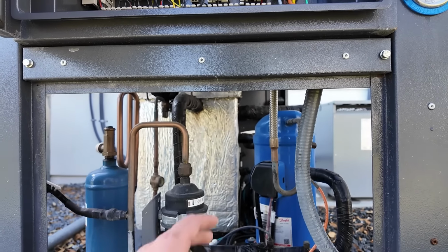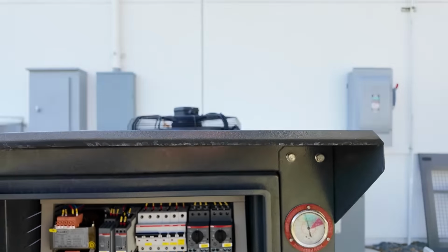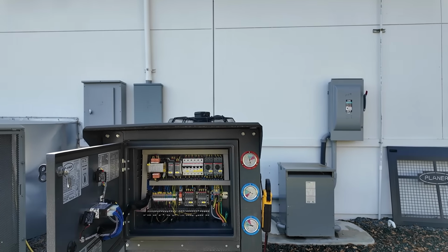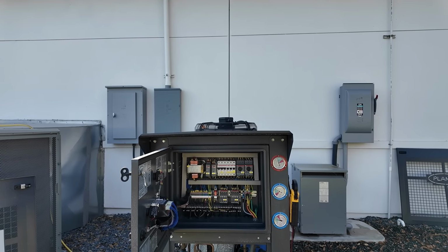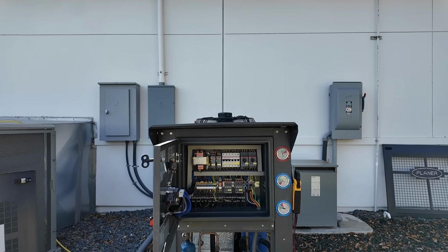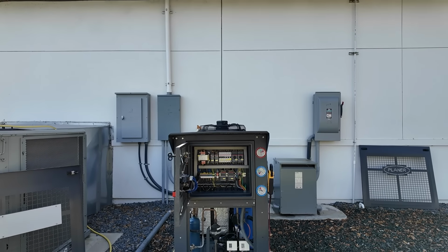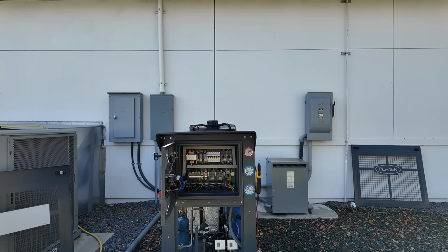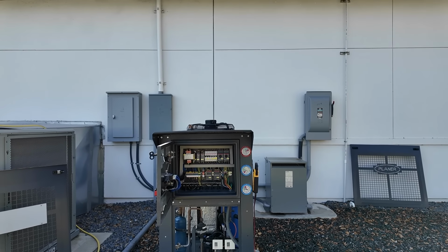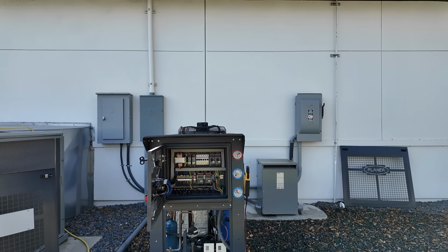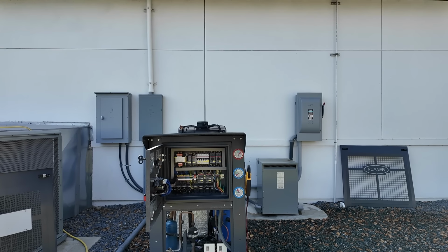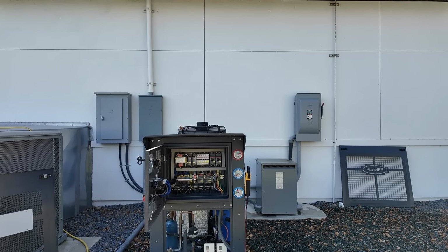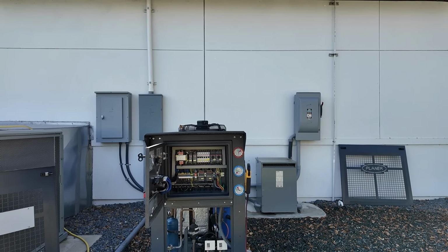Again, we don't recommend pouring water on high voltage. But for something like this, you want to make sure that we don't trip off from a nuisance alarm on something I know isn't really an issue. With power cycling the system a few times, we found that the system was just adding more and more heat to the water over time, which wasn't allowing me time to actually get the system running to combat that heat. Bit of a system design flaw if you ask me, but with it now, everything is running and we don't have any issues. Thanks for watching.